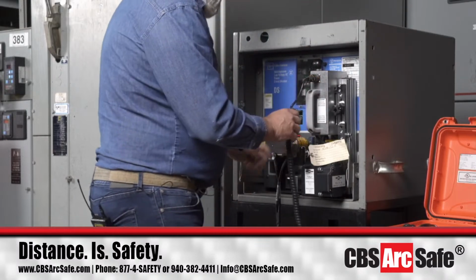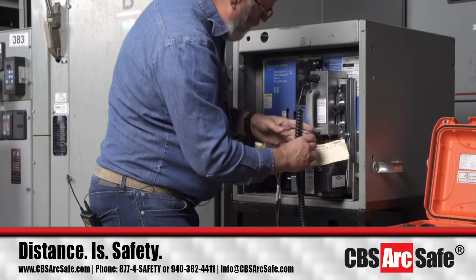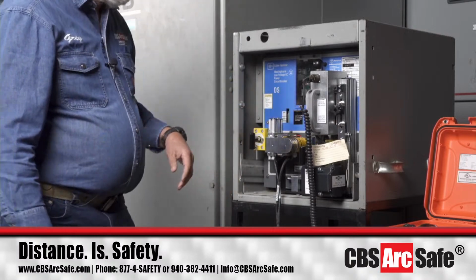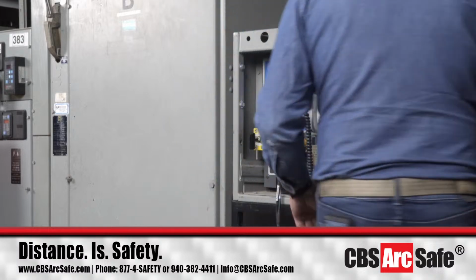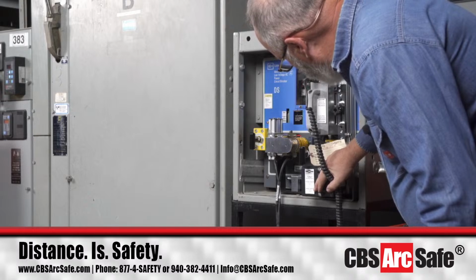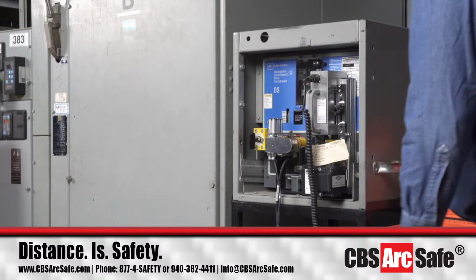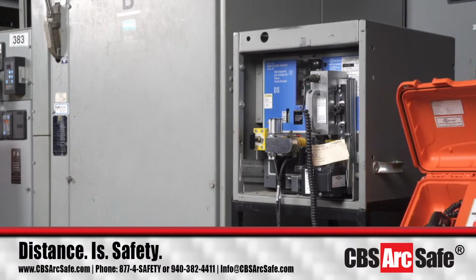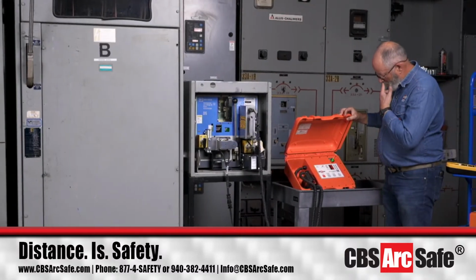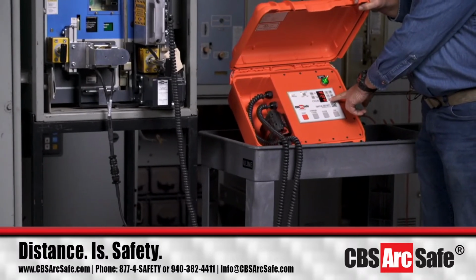Okay. So we're operating manually, so we've got this in the upper position here. We've got the solenoids lined up properly right here. The RSA will say on it for manual operation, cycle 1, T1 7.5, T2 7.5. So now I'm going to take my RSA, I'll turn it on. It says 7.5, 7.5, 1. Can you see that, Brian?